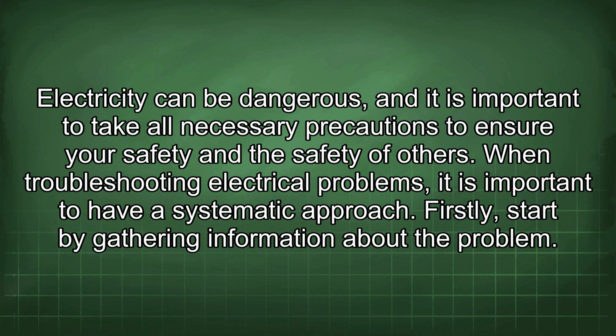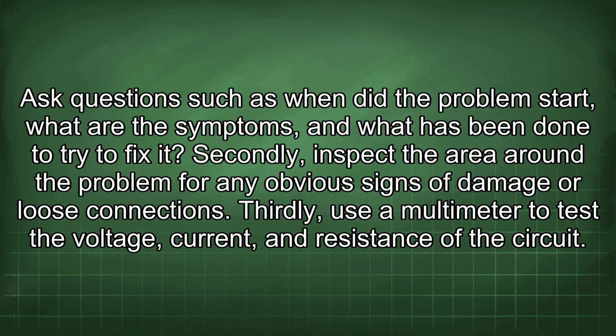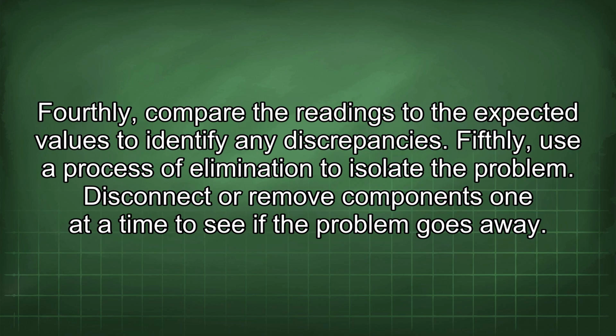When troubleshooting electrical problems, it is important to have a systematic approach. Firstly, start by gathering information about the problem. Ask questions such as when did the problem start, what are the symptoms, and what has been done to try to fix it. Secondly, inspect the area around the problem for any obvious signs of damage or loose connections. Thirdly, use a multimeter to test the voltage, current, and resistance of the circuit. Fourthly, compare the readings to the expected values to identify any discrepancies.